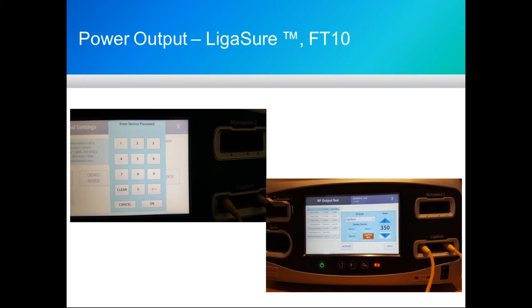Okay, now we'll go into the high-frequency testing. High frequency testing is required. I know a lot of people ask, and it is required, and it's for patient safety. The basic rule is, if you don't want to hook your mom to the unit, you don't want to be a biomed. Sorry, that's how I was raised a long time ago. Patient safety is the number one job of a biomed, and that's why you want to test the high frequency.